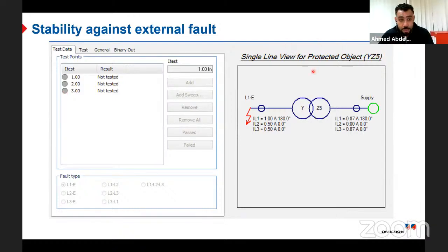So what I'm going to do is, I'm just entering the data of a transformer, and I will simulate a fault with any value. Here I simulate a fault with 1 I nominal, so the transformer will carry the full load current, then 2 full load, 3 full load, and I can go for 100 full load if my relay can withstand it, and also my CMC can inject. Then I'm just injecting and seeing.